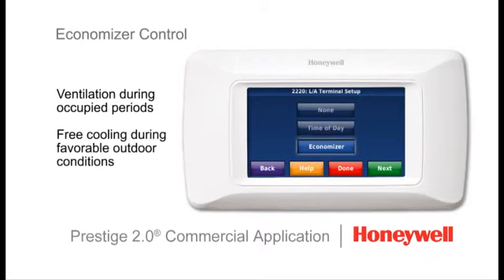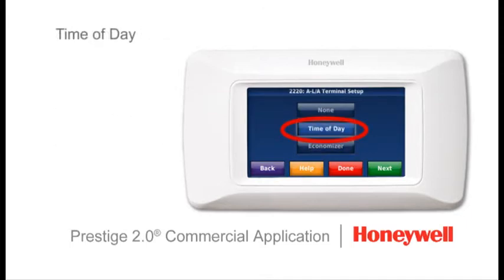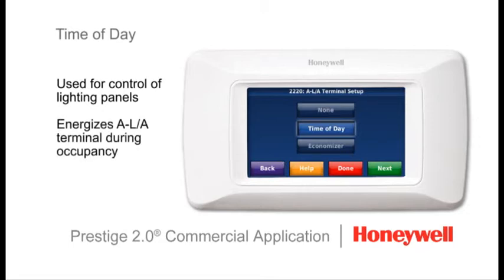The economizer module connects to the ALA terminal at the thermostat or Equipment Interface module. Prestige 2.0 can also be set up for time of day output in the installer setup. Time of day output is commonly used for the control of lighting panels. When set up for time of day, the ALA terminal is energized during occupied periods.